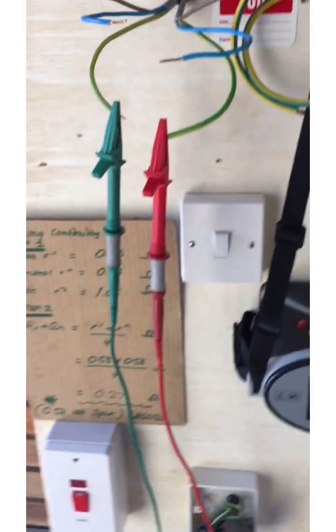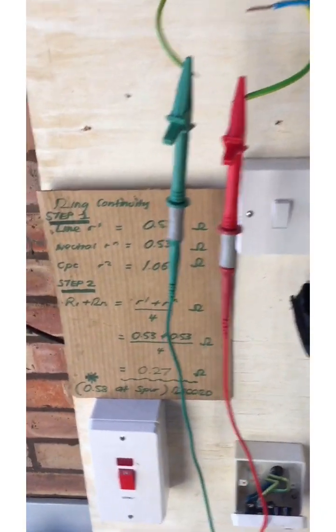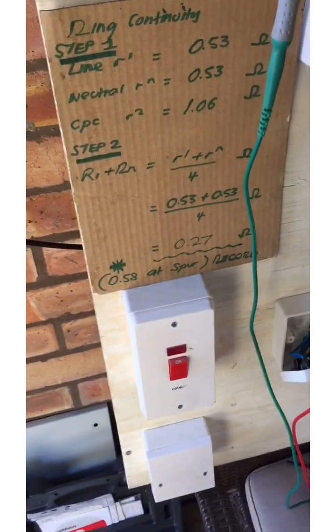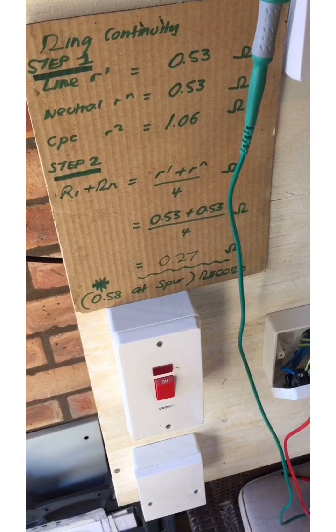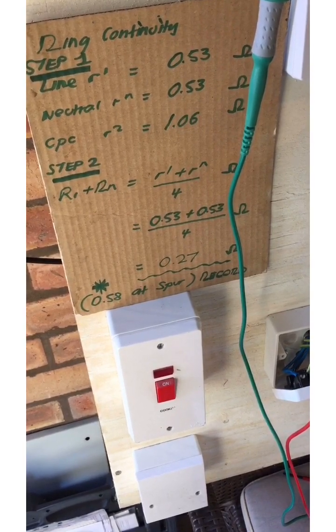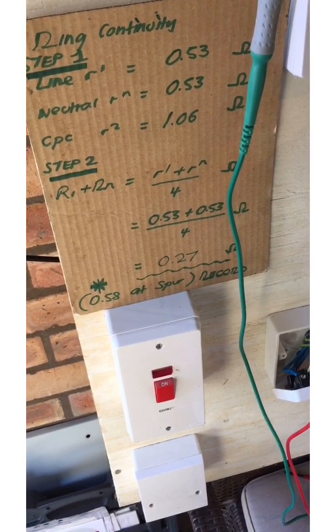So step one, end-to-end resistance. They're the values that I got previously, not a million miles away from what I got second time round. So the line was 0.53, neutral 0.53, and the CPC 1.06.